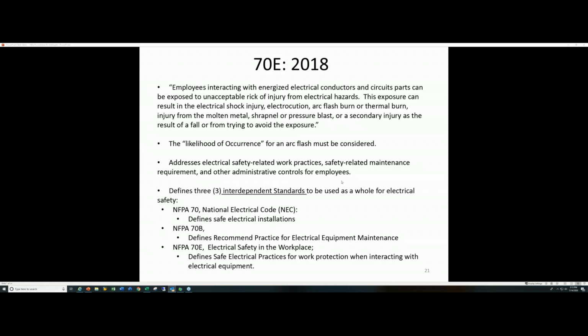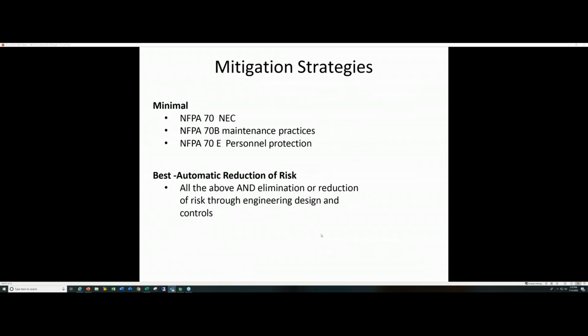So all three of these, I often hear people reference, well, I comply with NFPA 70. Well, okay, do you comply with 70E and 70B? Because they all make up what we call one electrical safety system. It's 70, design it right. It's 70B, maintain it right, and 70E, when you have to interact with it, this is how you can do it safely. So those are your mitigation standards. The minimum that we do and should be doing are 70, 70B, and 70E.